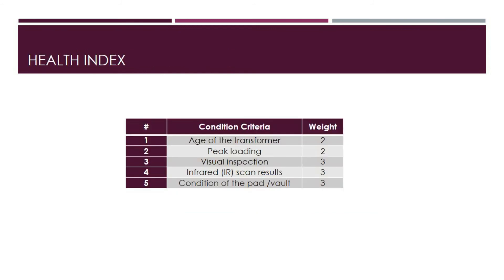Now let us look at the health index weights. We assign the condition criteria — age of the transformer and peak loading — a weight of 2. The visual inspection, the IR scans, and the condition of the pad or vault for pad mount or vault transformers are weighted with a weight of 3.